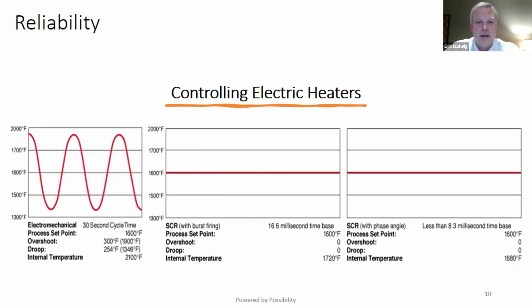On the far left-hand side, you see a typical on-off control system. The on-off control system will turn power on for a period of time and then turn it off for a period of time, which creates these swings that look more like a sinusoidal signal than a good, even, steady outlet temperature. In this particular example, we're using a process set point of 1600 degrees Fahrenheit, which produces an internal temperature in the heating elements themselves of about 2100 degrees Fahrenheit. So the important aspect to the reliability is that internal temperature of the heating element. That's what defines the life of the heating element. The lower that we can operate those heating elements, the more life you're going to have in the system.